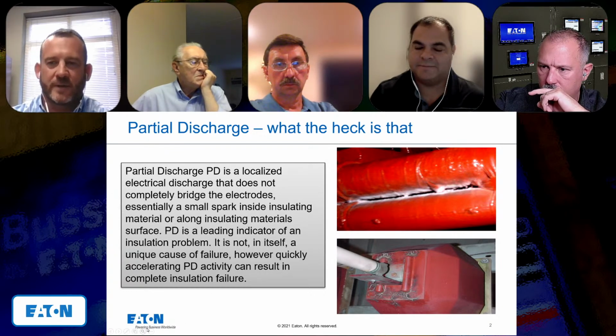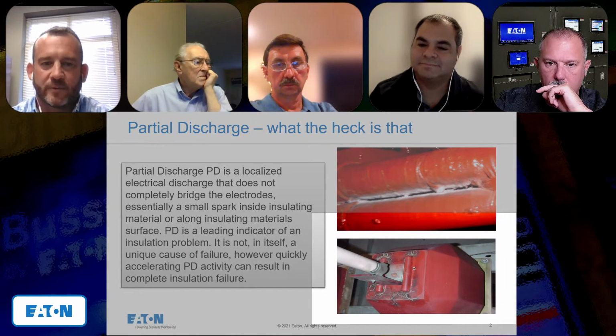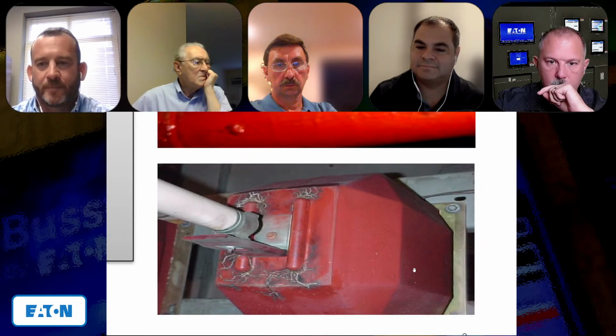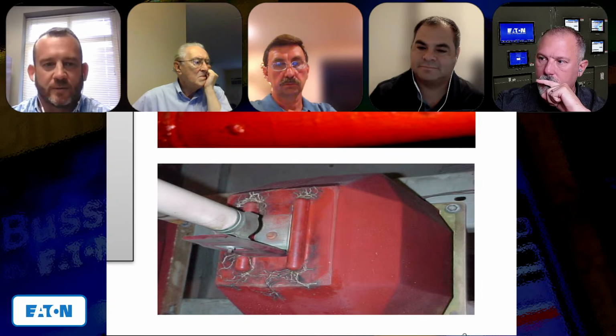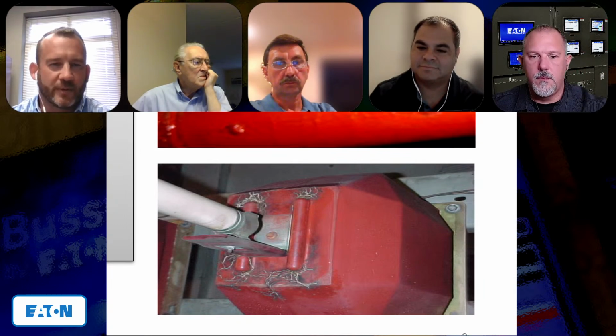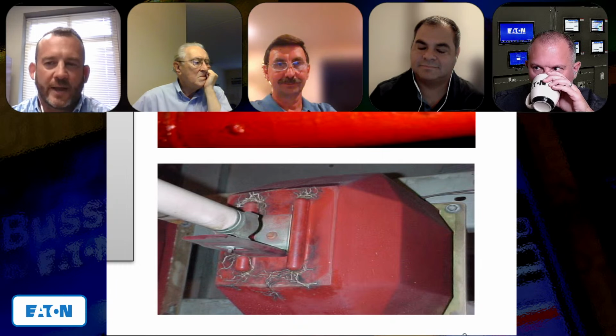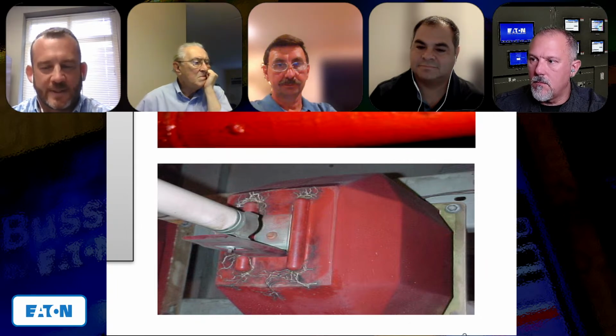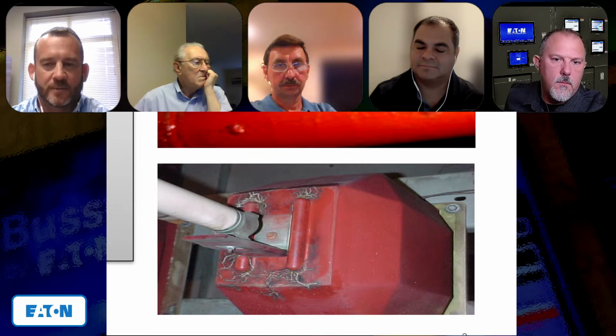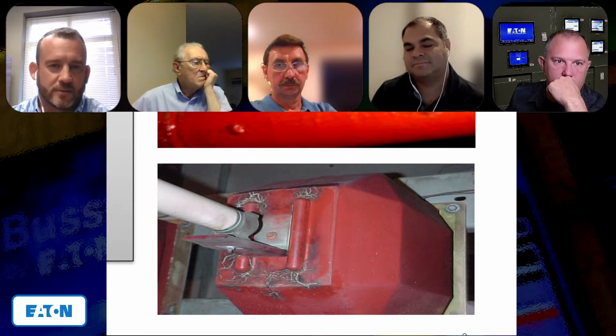Some of the things you'd see in medium voltage switchgear or medium voltage motor control centers - that bottom picture shows, I believe, a potential transformer, but it has the tracking effect, that black carbon, where the voltage - contaminated by oil, dust, and different environmental items - is starting to break down that insulation.